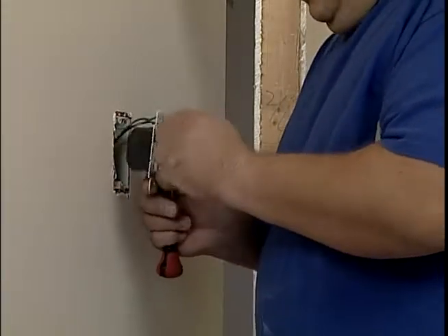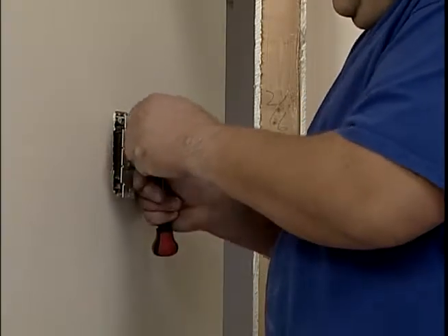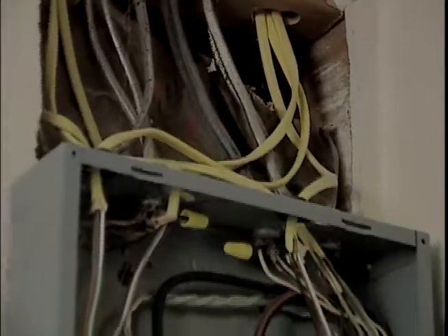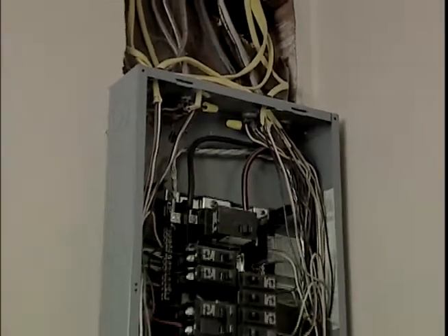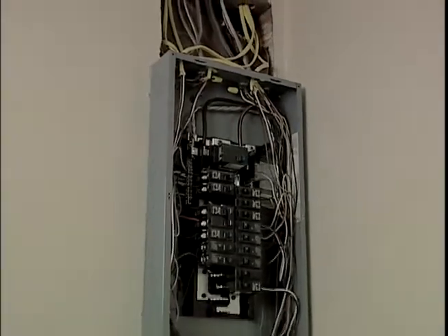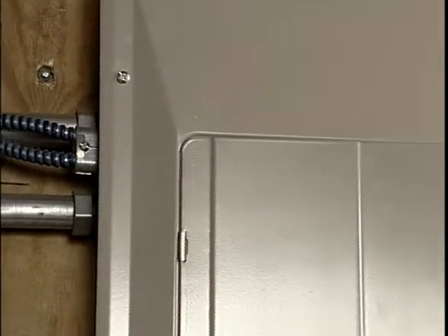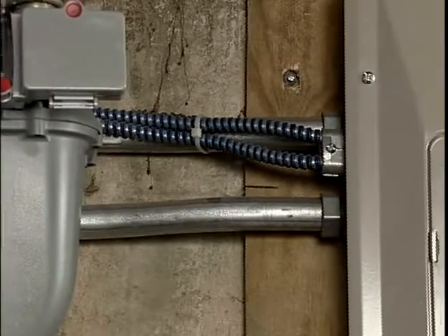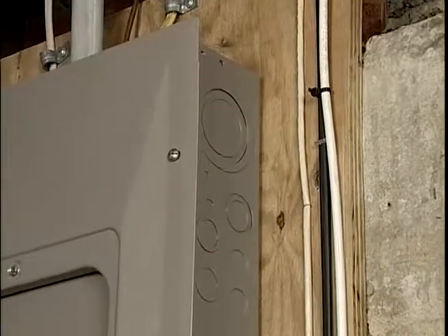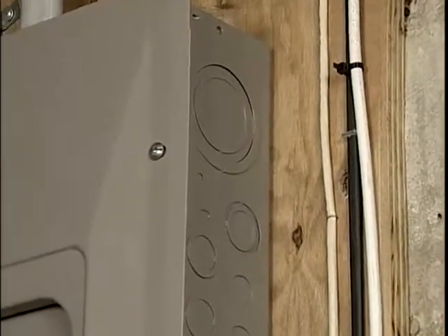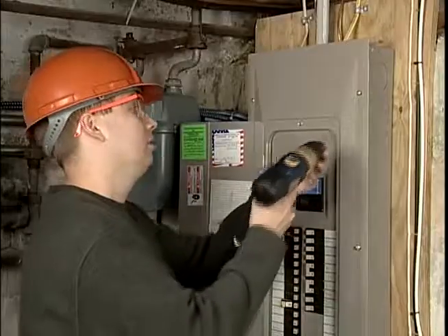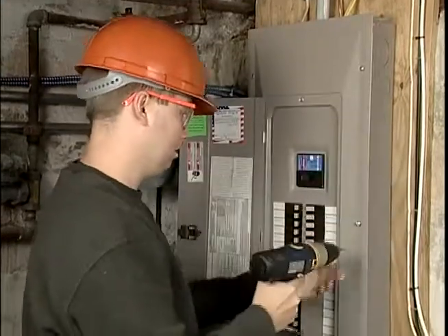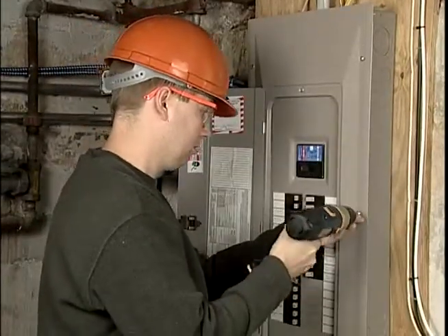Another responsibility that employers have is to make sure that electrical parts, outlets, and power supplies are controlled and protected appropriately. Parts, wiring going into circuit breaker boxes, and cabinets and fittings should all be protected from abrasion. Openings through which wires enter circuit breaker boxes and cabinets must be effectively closed around the wires themselves. Likewise, unused openings in cabinets, circuit breaker boxes, and fittings must also be closed off. Employers must also ensure that all fittings, circuit breaker boxes, and pull boxes are covered. Metal covers must be grounded.